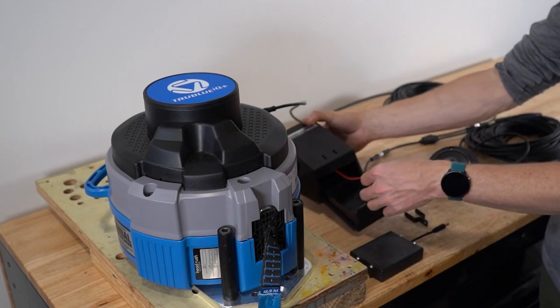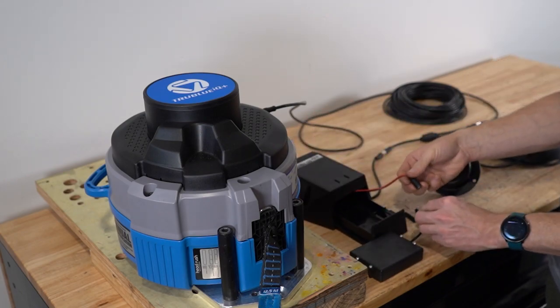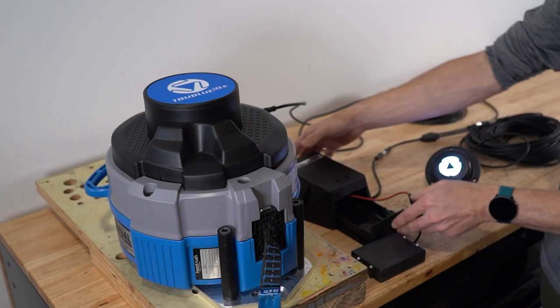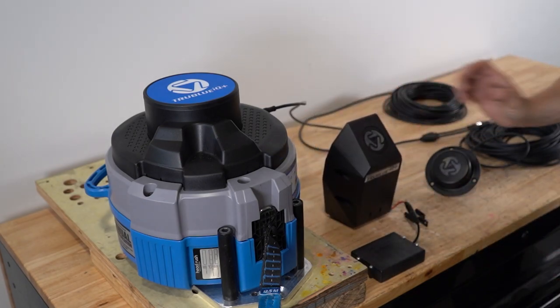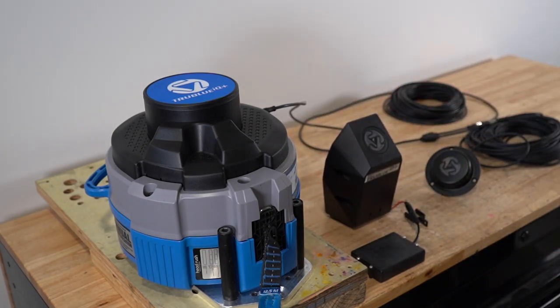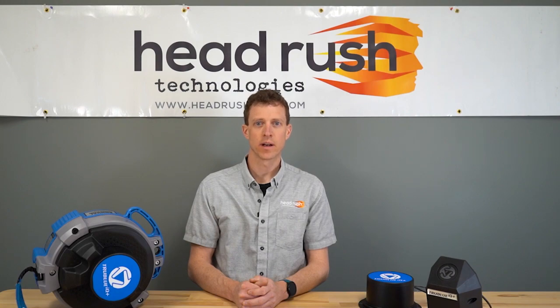Right away, you should notice that the lights are on and the device is running an electronics check. Once this check is complete, the lights should flash green. Depending on how long you have charged the battery pack, it's possible that the battery level is too low. In this case, you'll need to charge the battery for a while longer before continuing with these tests.